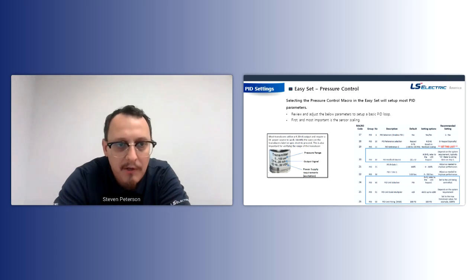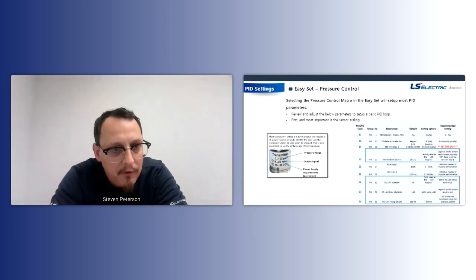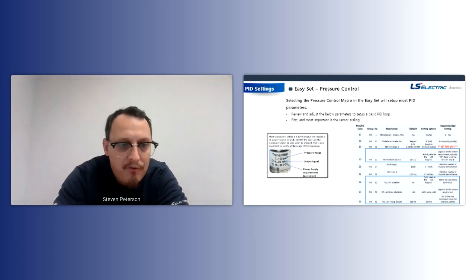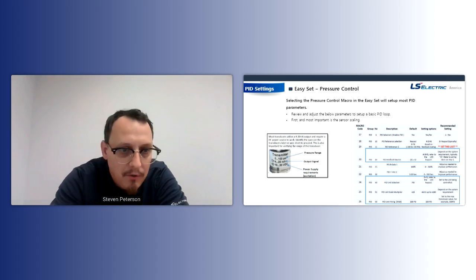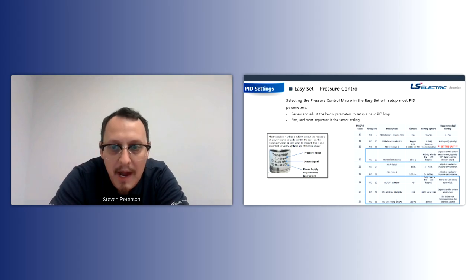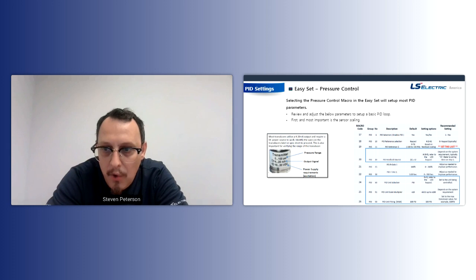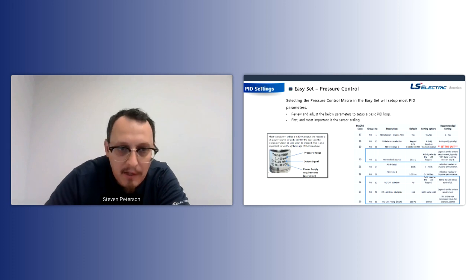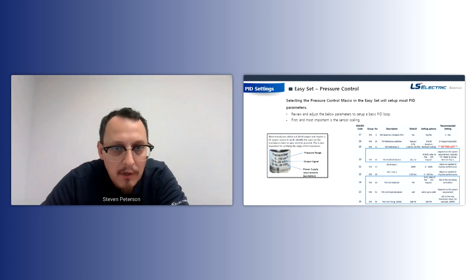So that's the first thing you want to do. Right here, we have a little picture of a 4 to 20 milliamp transducer. It's a pressure transducer that's rated from 0 to 100 PSI. The first thing you're going to do is set the feedback source here to be I2, because it's a 4 to 20 milliamp. So I for current. Then you're going to go to the scaling and set it to 100 PSI.